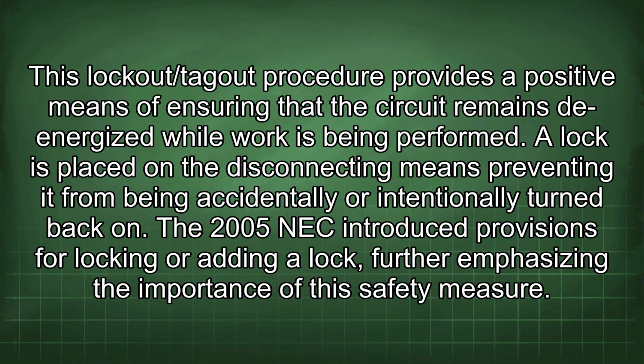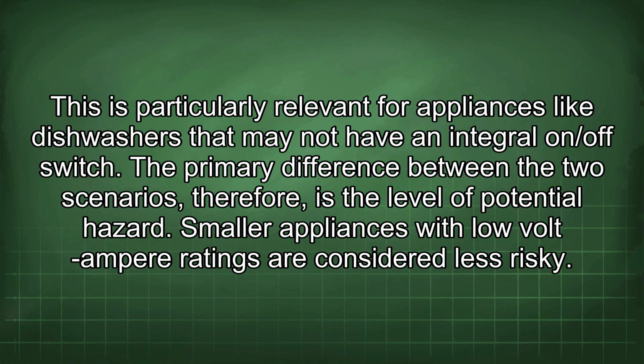A lock is placed on the disconnecting means, preventing it from being accidentally or intentionally turned back on. The 2005 NEC introduced provisions for locking or adding a lock, further emphasizing the importance of this safety measure. This is particularly relevant for appliances like dishwashers that may not have an integral on/off switch. The primary difference between the two scenarios, therefore, is the level of potential hazard.